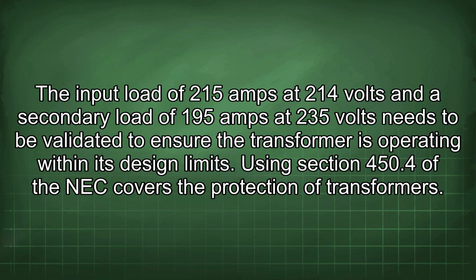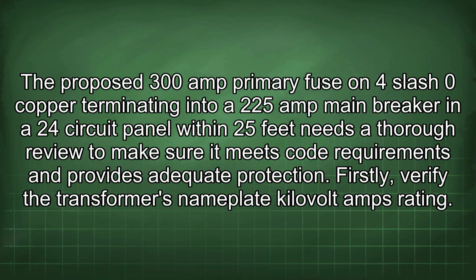Section 450.4 of the NEC covers the protection of transformers. The proposed 300 amp primary fuse on 4/0 copper terminating into a 225 amp main breaker in a 24 circuit panel within 25 feet needs a thorough review to make sure it meets code requirements and provides adequate protection.